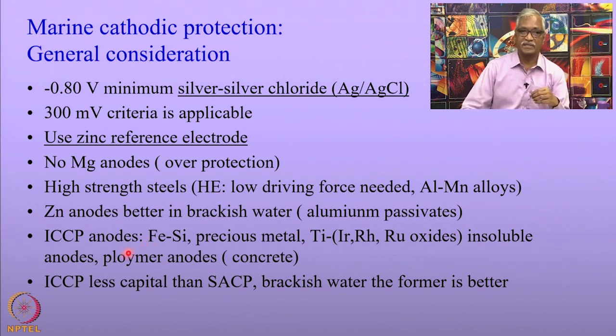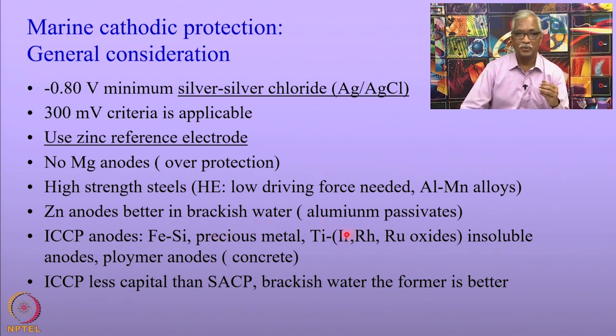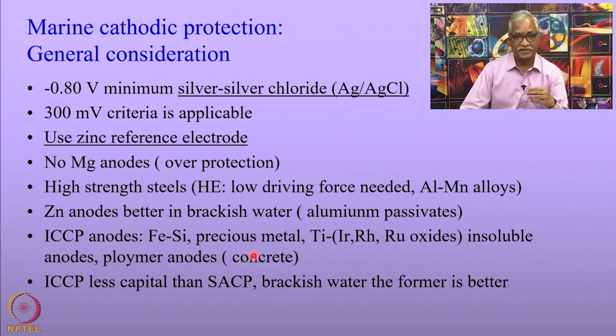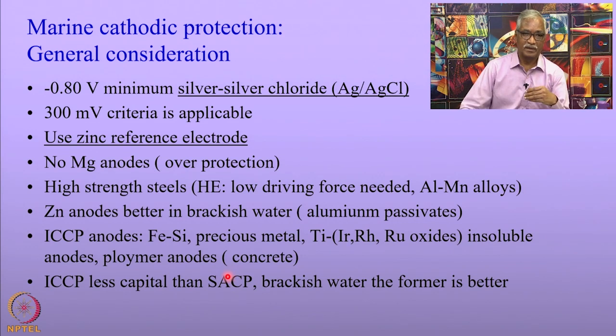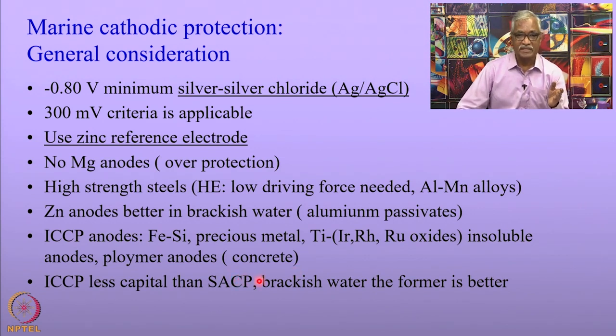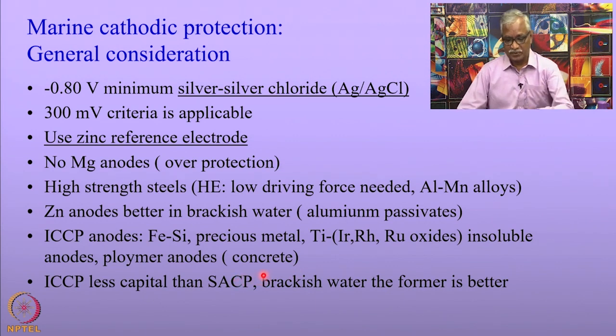If ICCP is used, iron-silicon, precious metals such as platinum, titanium insoluble anodes, or polymer anodes are used where there are concrete structures. ICCP is less capital-intensive than sacrificial anode cathodic protection systems for seawater applications because large amounts of sacrificial anodes would otherwise need to be installed. For brackish water, ICCP works better than sacrificial anode systems.